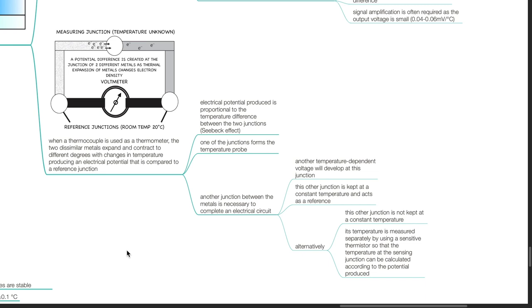One of the junctions forms the temperature probe. Another junction between the metals is necessary to complete an electrical circuit, and another temperature-dependent voltage will develop at this junction. This other junction is kept at a constant temperature and acts as a reference. Alternatively, this other junction is not kept at a constant temperature; its temperature is measured separately by a sensitive thermistor so that the temperature at the sensing junction can be calculated according to the potential produced.